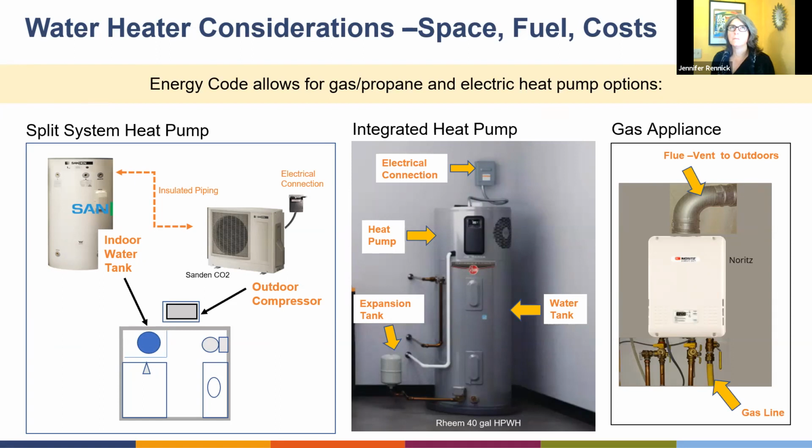A lot of the heat pump water heaters commonly are a 30 amp 240 dedicated circuit, but Rheem's coming up with a 15 amp there that you could just plug in essentially. So 15 amp 120. So right. Yeah, it seems like the manufacturers realize that we need something that's pretty easy to get installed. Yeah, definitely.